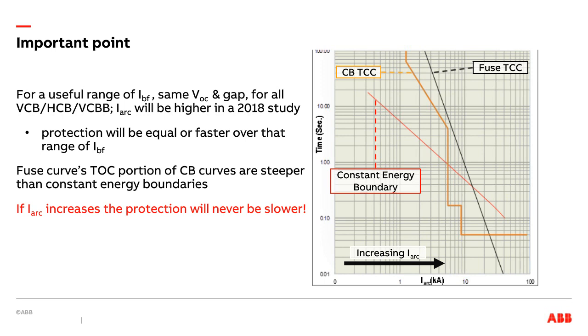So in theory, if you want to do this correctly, you need to examine the gear and identify the actual gap. And the new model allows you to choose the exact gap. So if you decide it's 33.5 millimeters, put in 33.5. However, the one thing you can also say is, if in doubt, if you're not sure if it's 25 or 32 or 40, use 40. That's conservative.